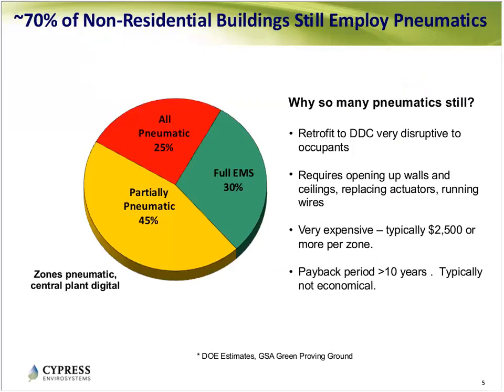So just how many pneumatic buildings are there? Those of you who work in or manage one already know there are a lot. It's probably around 70%, based on data from the DOE and U.S. federal government sources—about 70% of non-residential buildings have pneumatic controls. That means 30% are fully digital, with digital stats, networks, and digital air handlers, chillers, and boilers. A good number are completely pneumatic with no digital systems at all—that's a shrinking segment, about 25%. The largest segment is buildings in the middle: they upgraded their chillers and air handlers, but it was too difficult and expensive to get into the zones and occupant spaces to disrupt them and replace the thermostats.